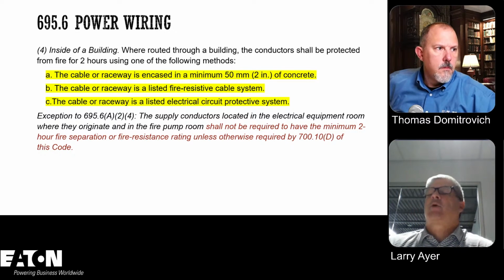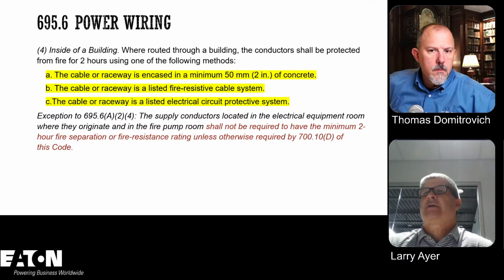And today, more and more people are starting to use listed fire resistive cable systems, something like, I think Draka makes it. It's an EMT with a 2-hour rated RHW cable inside. People still use MI cable, that's 2-hour rated, but I see more and more people using other types of EMT with specialty cables inside.